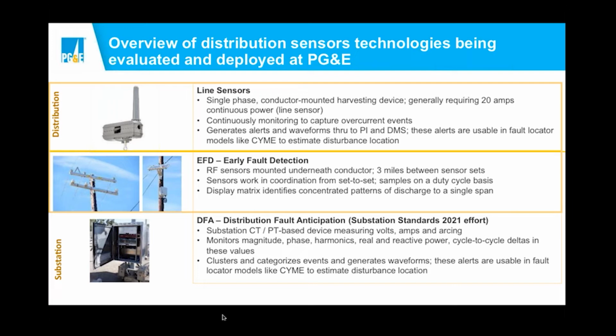The last one listed here is DFA technology, distribution fault anticipation. These are current transformers and potential transformers installed at substations to monitor waveforms on the entire line segment from the substation. The waveforms are then classified to understand the types of faults occurring on the line.